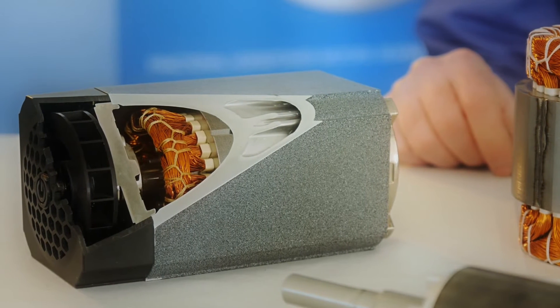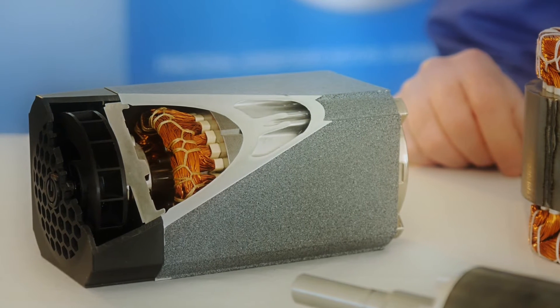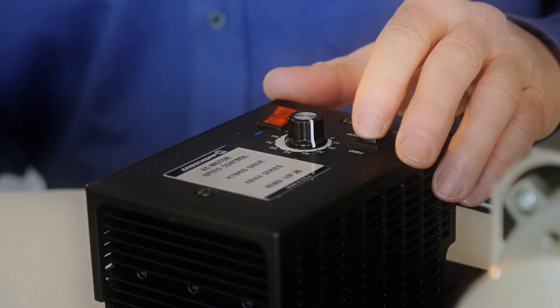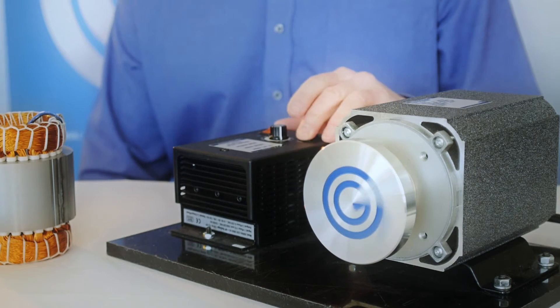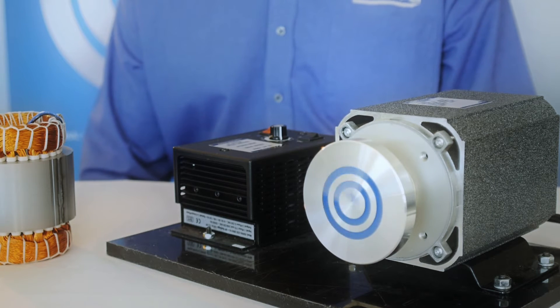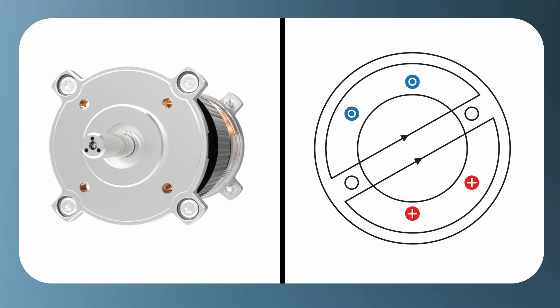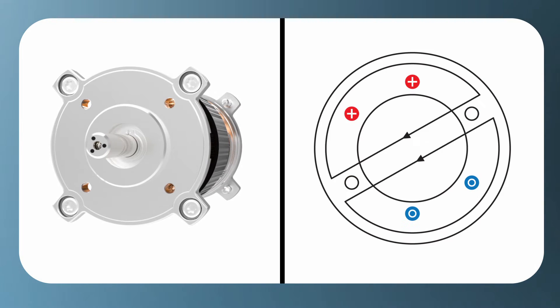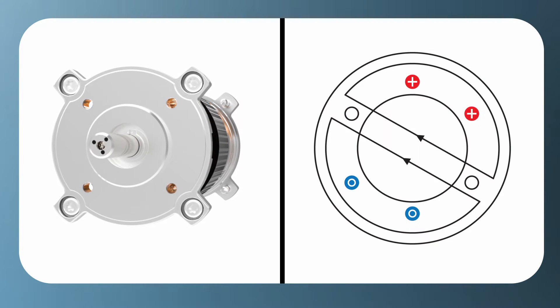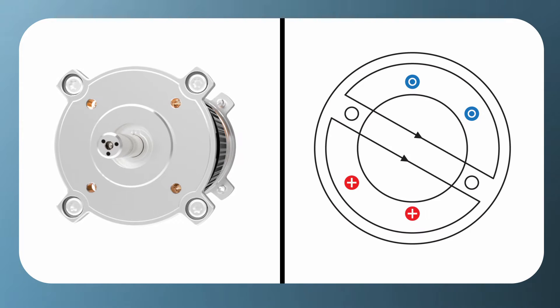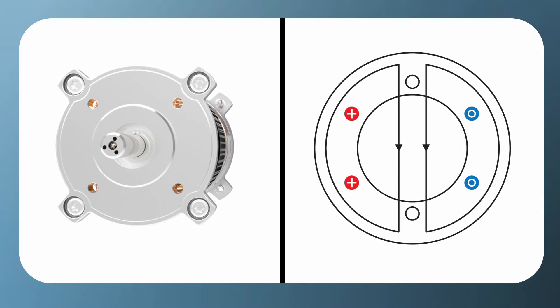In three-phase motors, the current in the stator sets up a rotating magnetic field as shown here. The magnetic field rotates due to the 120-degree phase offset in each phase of the power supply. This rotating magnetic field induces a current in the bars of the rotor. The current in the rotor sets up its own magnetic field, and the interaction between the stator and rotor magnetic fields causes the rotor to rotate.